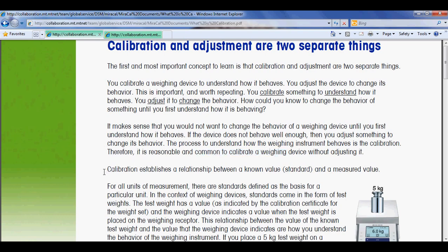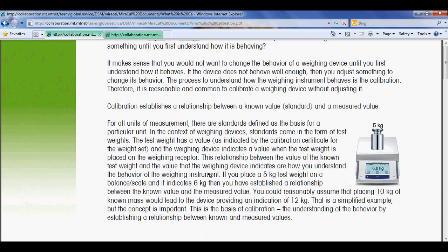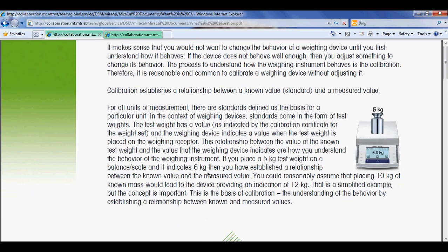Okay, and then more specifically, calibration, so developing that understanding of a measuring device, calibration establishes a relationship between a known value, or the standard, and a measured value. And that's how we develop the understanding of how it behaves. And it's important that that known value is a traceable standard, such as the test weights that we all use to carry out calibrations. At the bottom of the page, there's a very simplified example saying that for all units of measurement, there are standards defined as the basis for a particular unit.